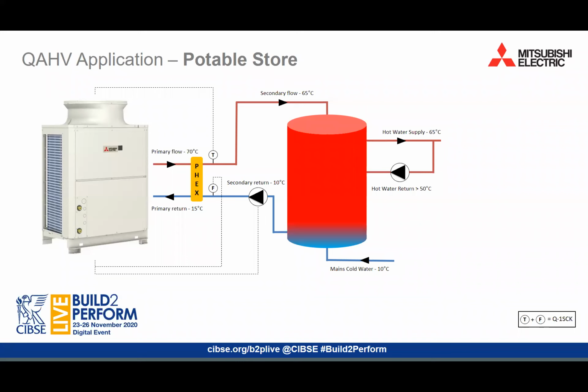The QAHV is supplied with an integrated primary side variable speed pump, which is capable of achieving an external head of 77 kPa at 17 litres a minute. The QAHV should be placed no more than 60 meters from the plate heat exchanger, and the primary circuit requires a minimum of 40 litres.